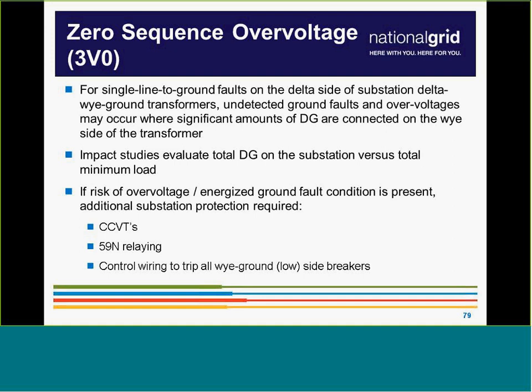And we have screens where we look for that. We built a little bit of margin in for smaller DGs, so that a 10 kilowatt system is not going to throw it, but the larger systems we'll definitely look at. If you fail the 3V0 screens, we need to install 3V0. What that is, is a set of CCVTs, and they're huge. I have no sense of scale, I've only seen pictures, but I haven't stood next to them. They're these big voltage sensors, capacitively coupled voltage transformers. And those go to a 59N relay, which we'll then use to trip all of the feeder breakers, so that we trip all of that DG off and de-energize the ground fault.